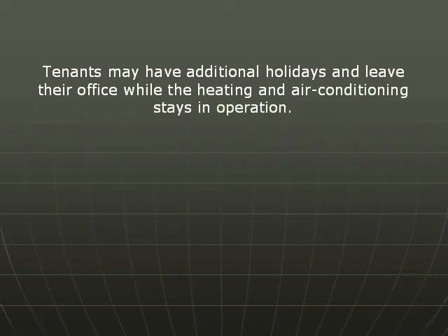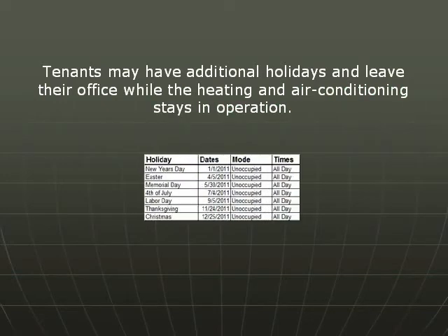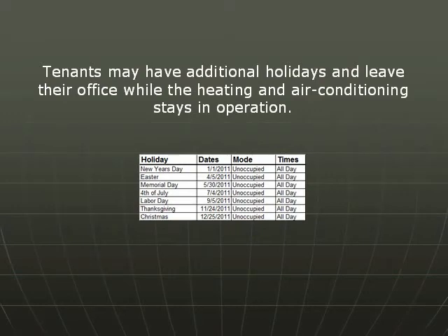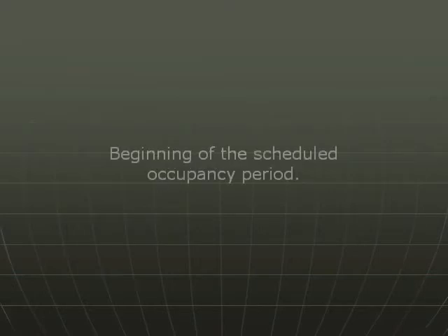Tenants may have additional holidays and leave their office while the heating and air conditioning stays in operation. Holiday schedules can be individually implemented and customized throughout the facility. The objective of optimum start control is to reach the comfort set point at the beginning of the scheduled occupancy period.